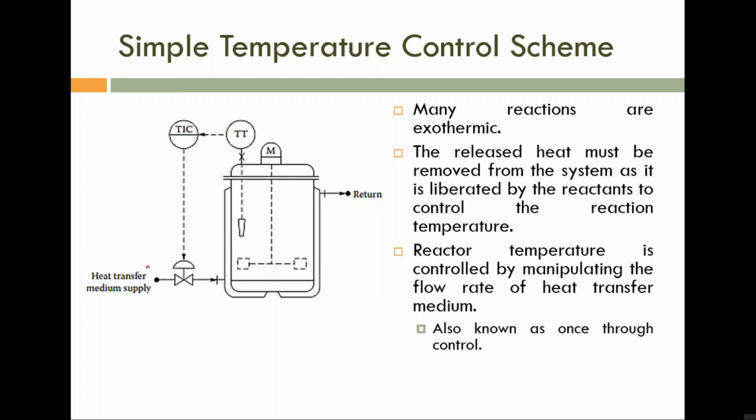Please note, the flow variation with respect to this control valve is not, for explanation, 0 to 1000 gallons per hour. Not that. It is something like 500 to 1000 or 800 to 1000. The minimum value is very large. The minimum flow rate must be large for maintaining a minimum Reynolds number. Otherwise, the Reynolds number will decrease.